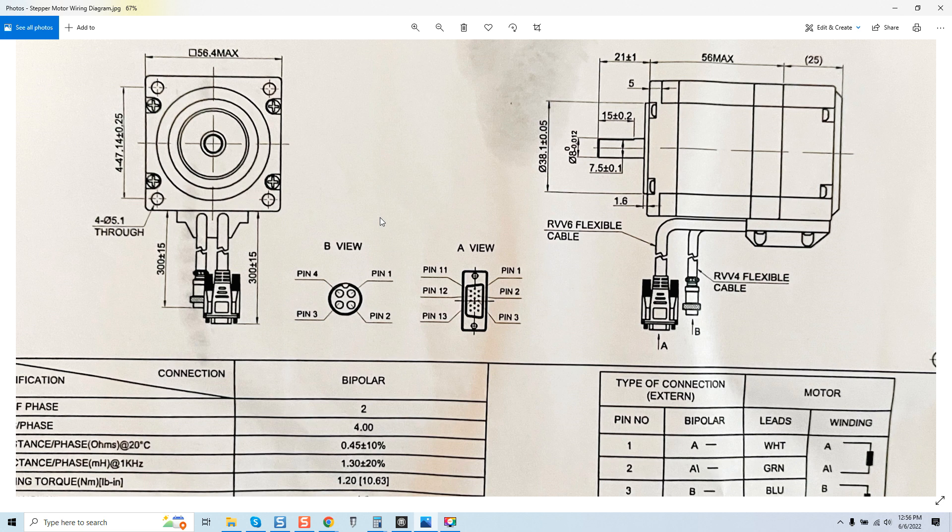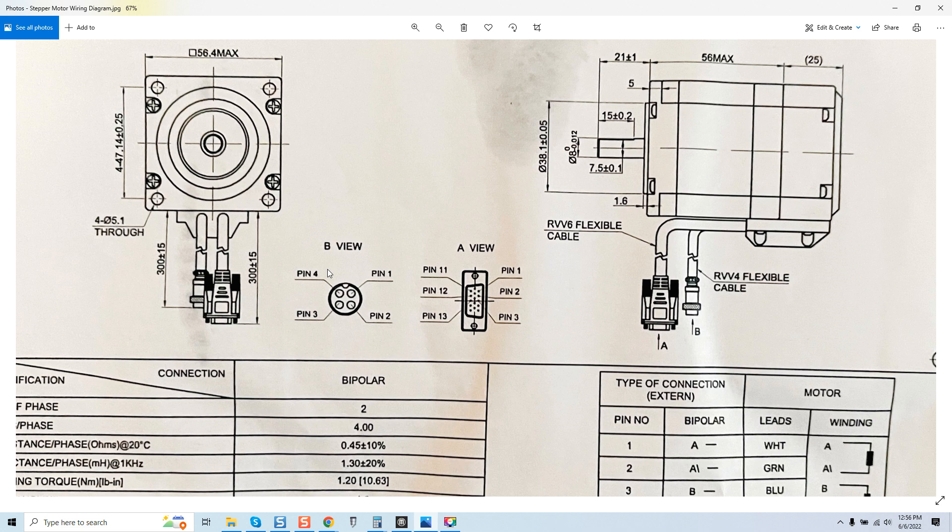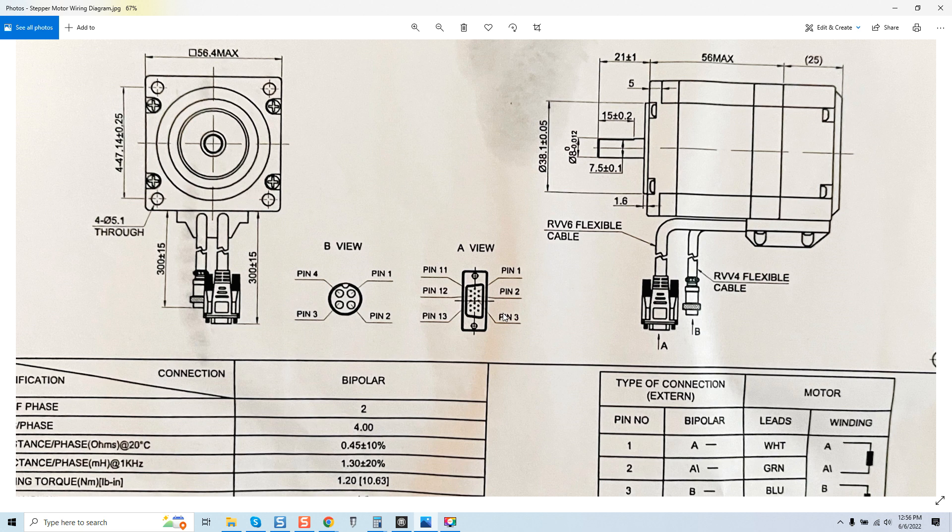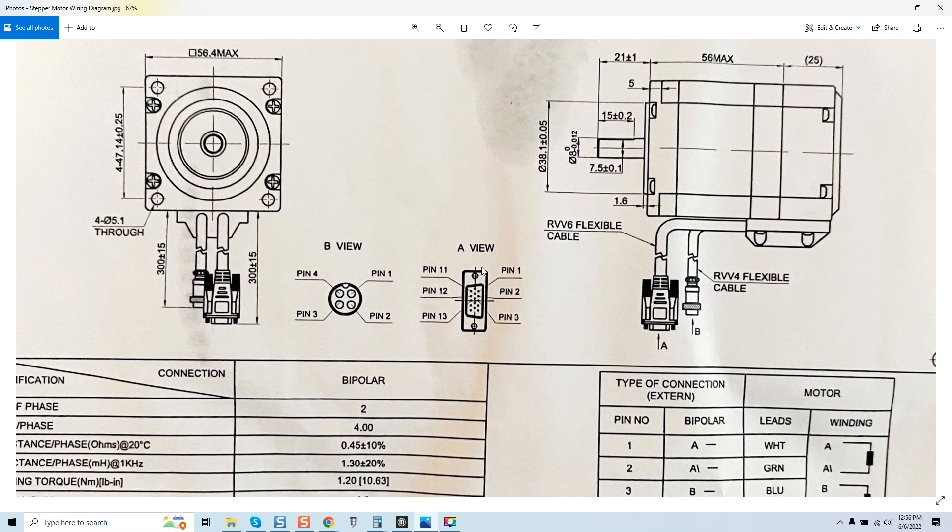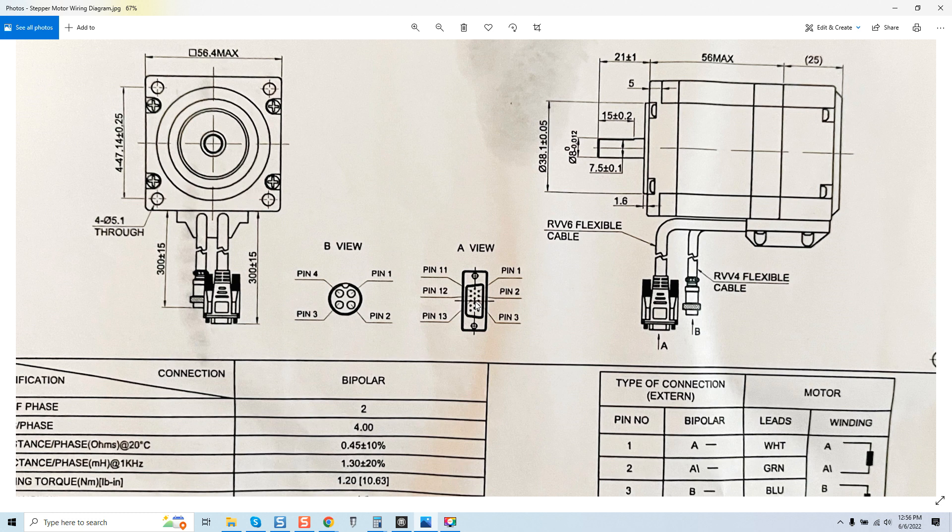The issue is that they're not looking at the variables that are missing and the two missing main variables are each motor if it's a closed loop stepper slash servo requires a motor cable which we see here on the B view on this drawing and under A view here you also require an encoder cable. So while you're getting the motor and the drive typically for about the same price you'd pay for a stepper motor stepper drive you now require the additional cables to accommodate this package and when you factor that in each motor requiring two cables instead of one.